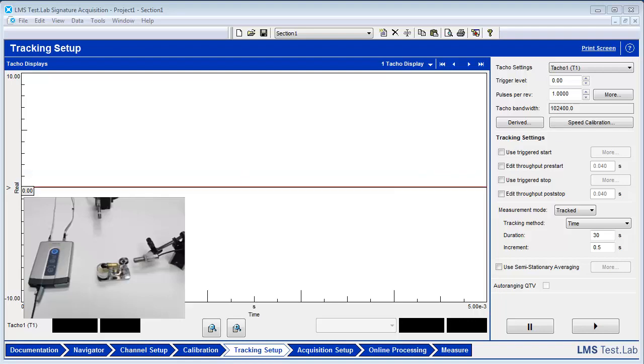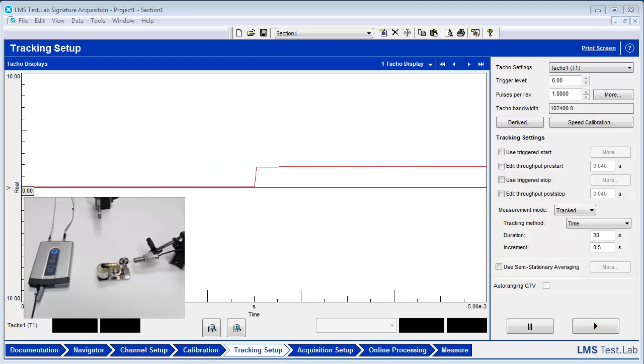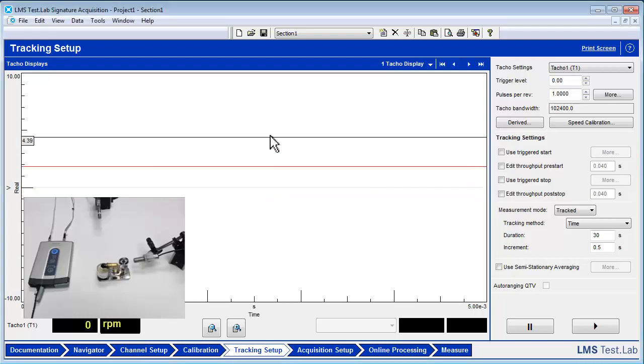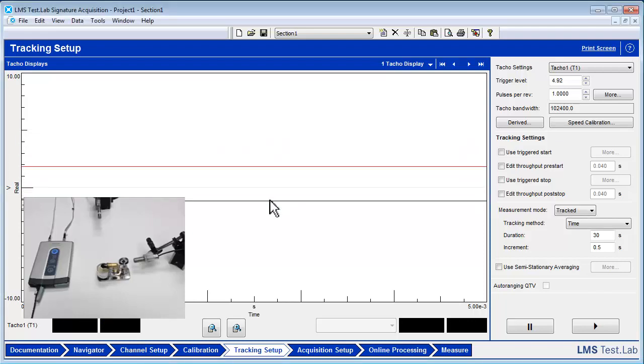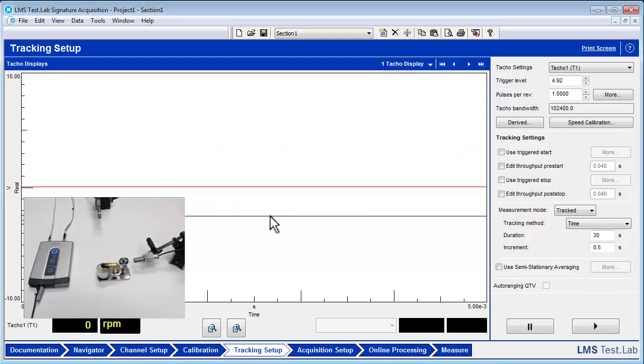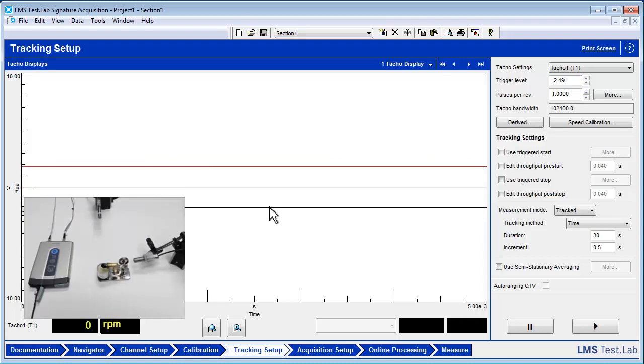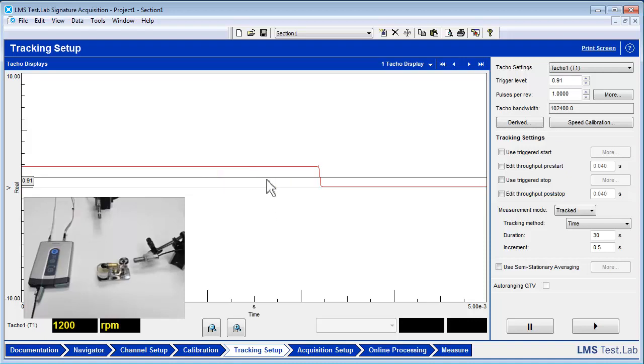A trigger level can manually be changed to fit testing needs by typing in a trigger value or moving the black bar in the window up or down. If a trigger is not set properly, RPM will be measured incorrectly. For example, if the trigger is set too high or too low, RPM will be calculated as zero. Set the trigger level to where the tachometer pulse passes through the trigger level. You should see an RPM being measured.